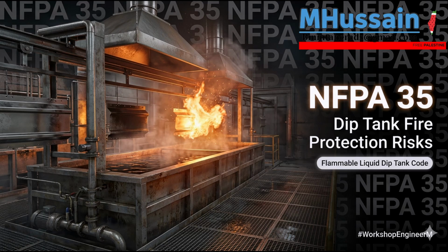Okay, I've always thought of it like lighting a traditional gas stove. Oh, that's a good way to look at it. Like when you turn the knob, you get that initial poof of gas igniting. That's the flash point, right? Right. But the fire point is the steady blue ring of flame that actually stays lit so you can boil your water. That is an excellent analogy, actually. For the layout engineers and fire protection designers, the flash point dictates the hazard classification of the room. So whether you need explosion-proof electrical gear or specialized ventilation. Precisely. But the fire point dictates the sustained intensity of the emergency you're going to be fighting if things go wrong.